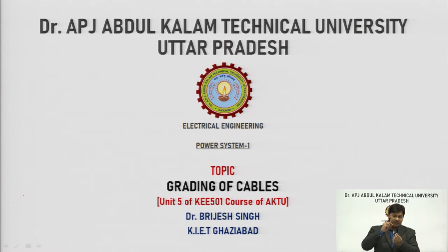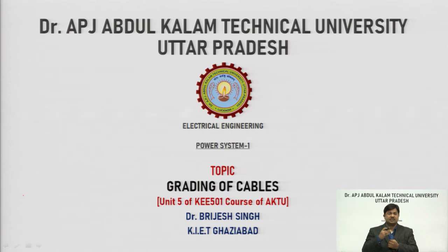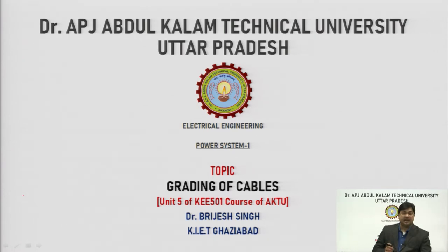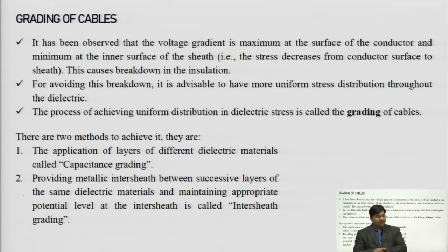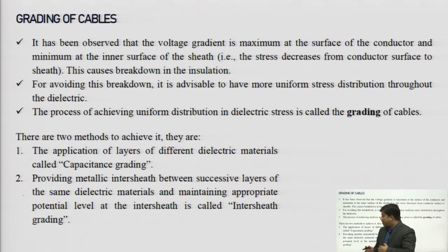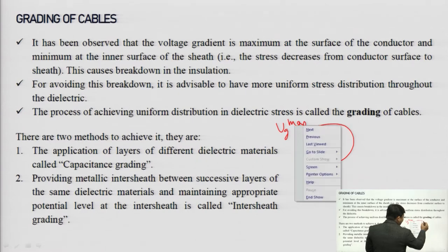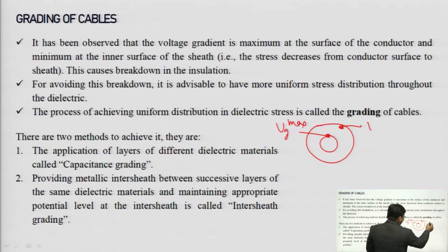The insulation from the center part to the upper surface is varying — it is not constant. Because of that, the dielectric stress in the radial direction from the inner side is different, and the voltage distribution across the entire insulation layer is non-uniform. At the core surface, the voltage gradient is maximum (g_max), and at the inner surface of the sheath it is minimum (g_min).